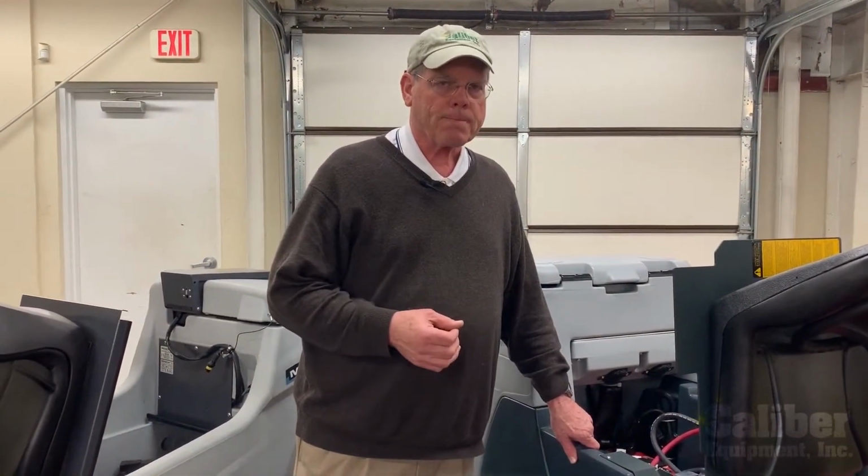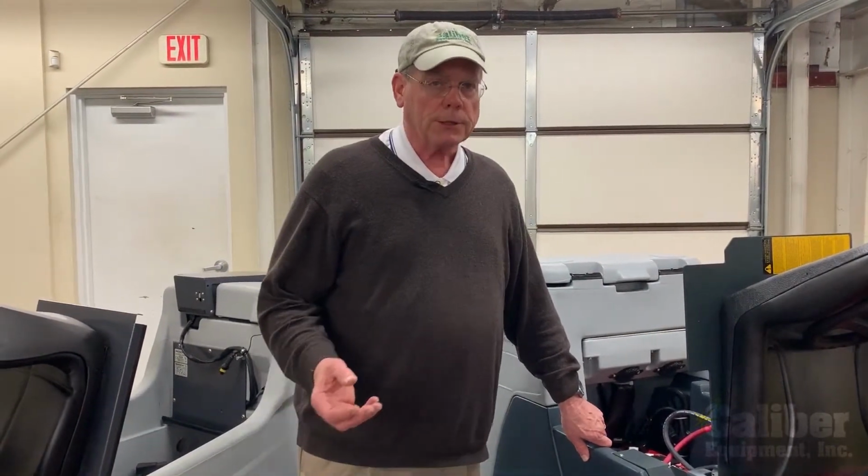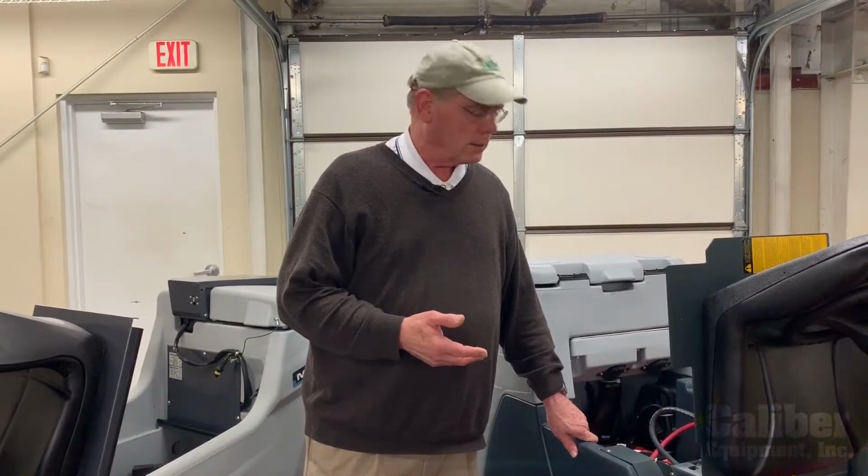disperse. So if you go back and charge it again, the charger itself is going to generate a certain amount of heat, which is going to reside in the batteries. At some point, you are putting too much heat in the battery. It's coming off a hot situation, and it's being heated again by the charger, and the result is that the liquids inside the battery will start to boil out of the battery and can be lost into the environment. Now, this may be just water vapor, which is not really dangerous to you or your people, but the loss of that water has to be replaced.